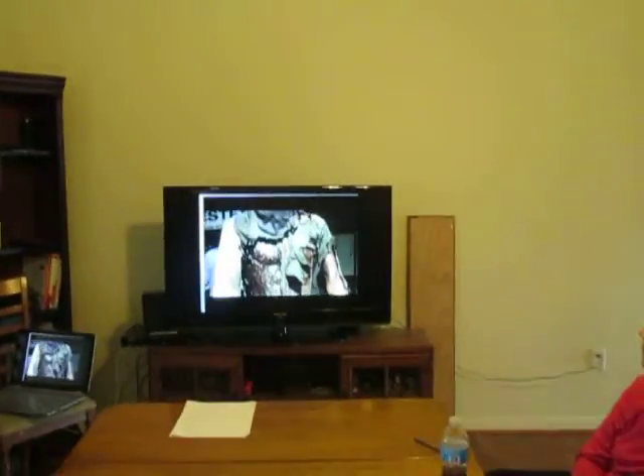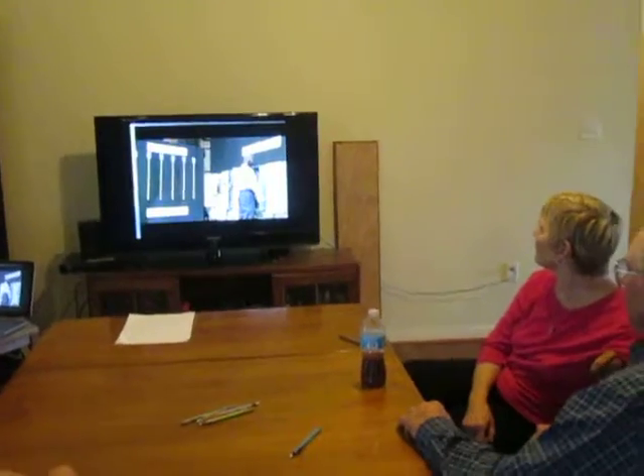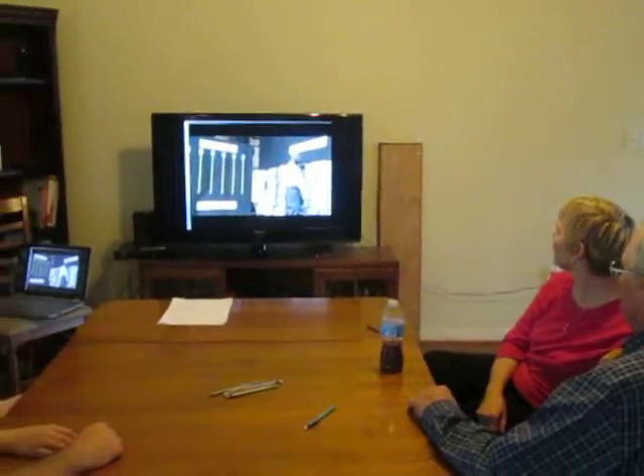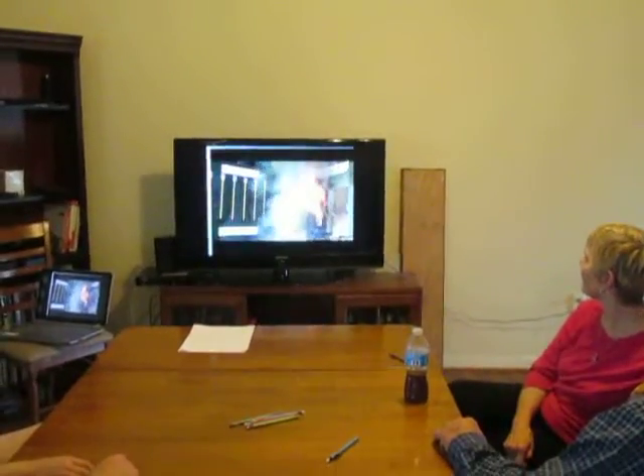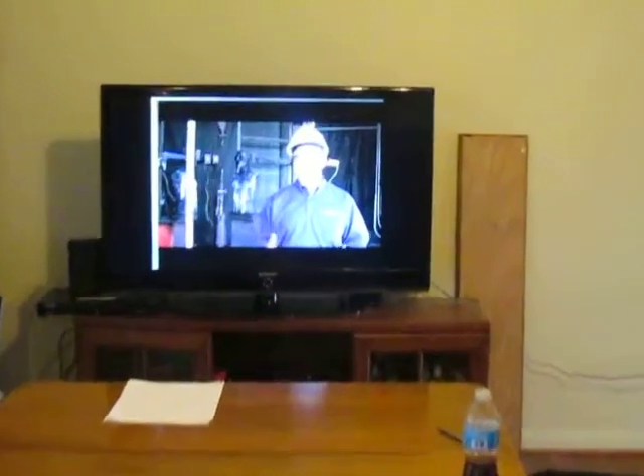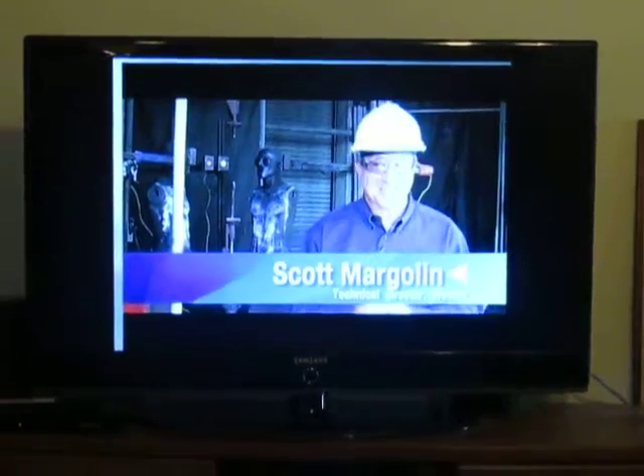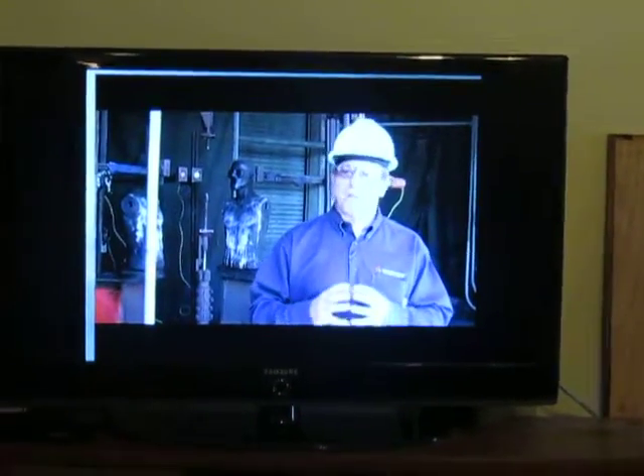The risks of an arc flash are hard to comprehend on paper, but when you see what happened in front of you, those risks are undeniable. What is an arc flash? An arc flash is a hazardous release of energy that's caused when electricity that should be inside the wire gets outside the wire, is a little bit of a simple way to put it, but now you have ionized air and plasma, and along with that, a shock wave or pressure wave, and any shrapnel that pressure wave might be pushing, and molten metal at 1900 degrees Fahrenheit or hotter, all of that coming at you at once.